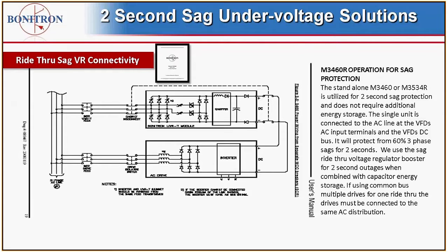The reason for this is we're using the AC line, or the remaining AC line, during a sag event to boost into the DC bus. So there has to be some remaining AC line to use just the single unit sag ride-throughs. And it's at least 40% cumulative across all 3 phases. You can lose one single phase AC as long as you have 70% remaining on the other 2 phases. There has to be something left for the ride-through to boost without energy storage.